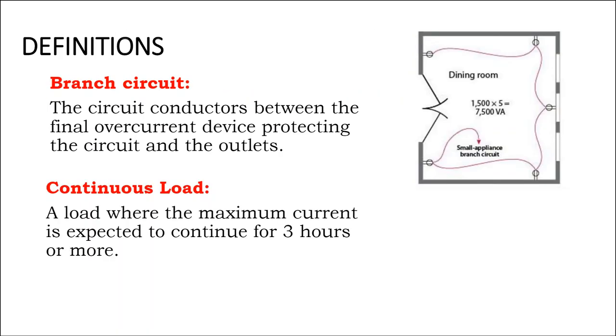If you have an appliance that might start up and spike up to 30 amps or 35 amps just for a minute or two and then drop down to 20 amps, your 20 amp cable can take the higher amperage for a very short period of time, provided that it actually goes away and the continuous load is where it drops down to.